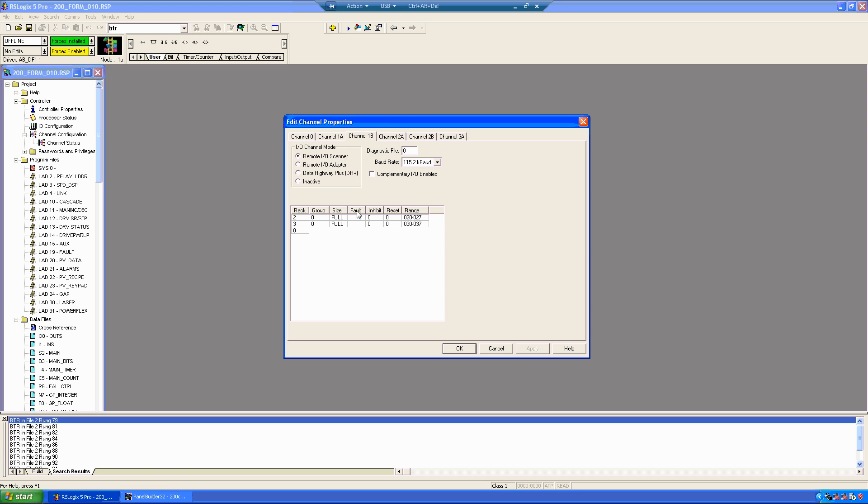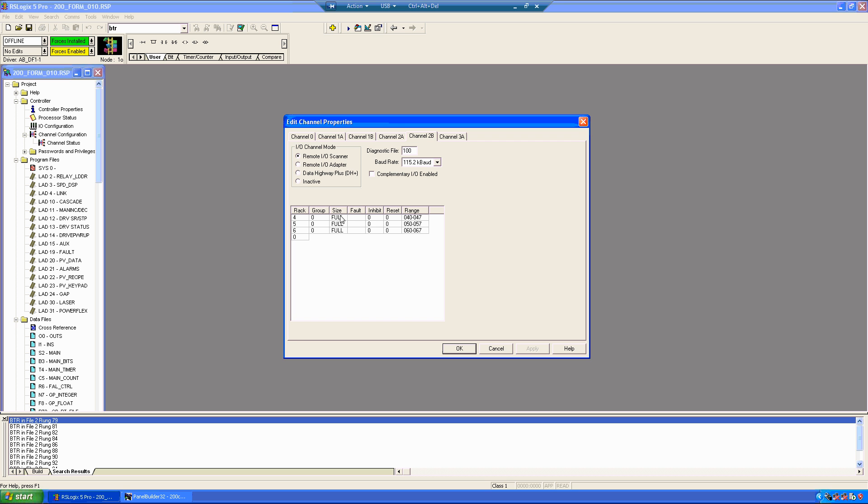So, let's just start with these here. So, what this is effectively telling us is, okay, rack 4, group 0, full size. So, basically we're taking the full rack, and the full rack would be 8 slots. Okay. And this is the I.O. words that are associated with rack 4.